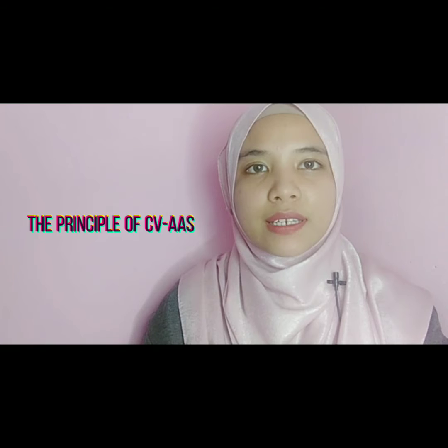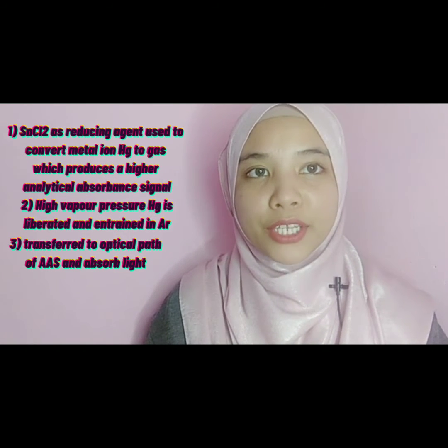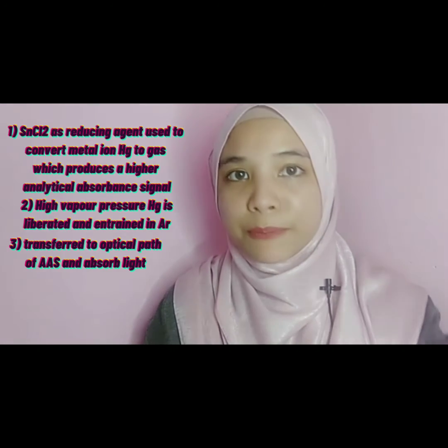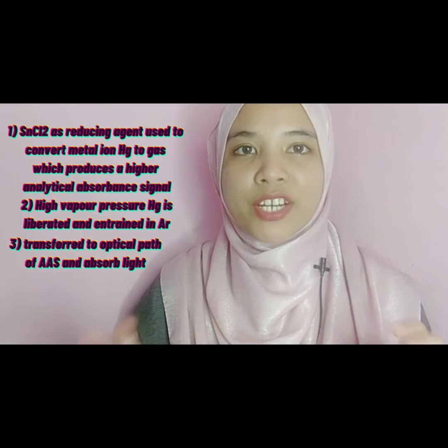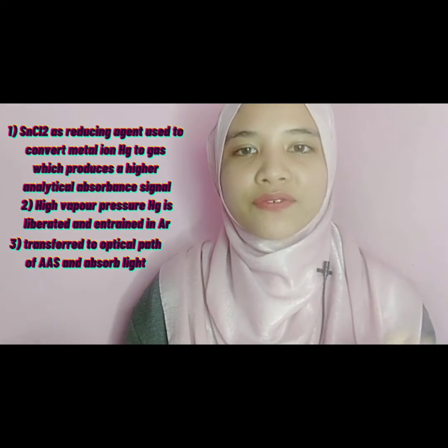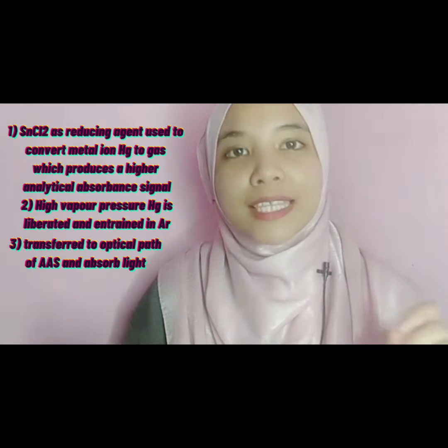The principle of this technique is that tin(II) chloride (SnCl2) as the reducing agent is used to convert the metal ion of mercury to gas, which produces a higher analytical absorbance signal. The mercury with high vapor pressure is liberated and entrained in an inert gas of argon and then transferred into the optical path of the atomic absorption spectrophotometer and then absorbs light.